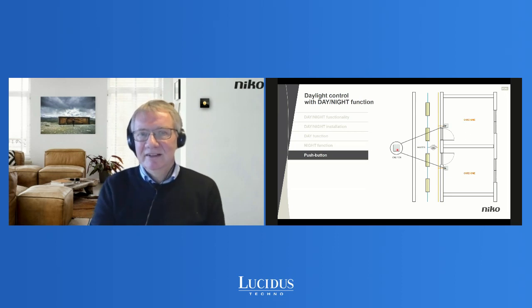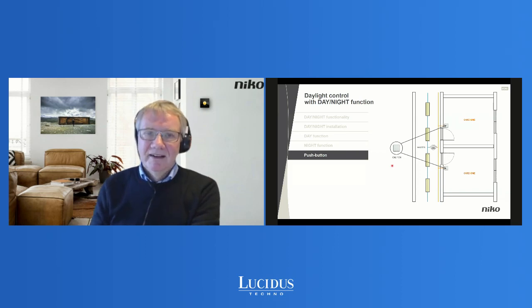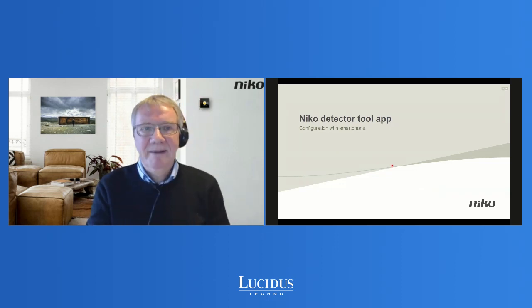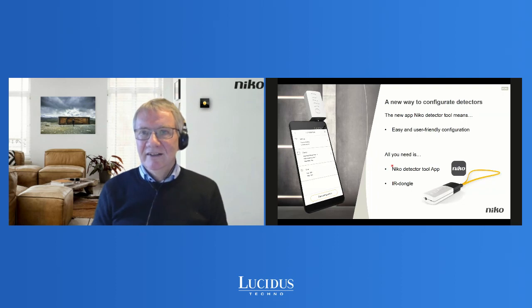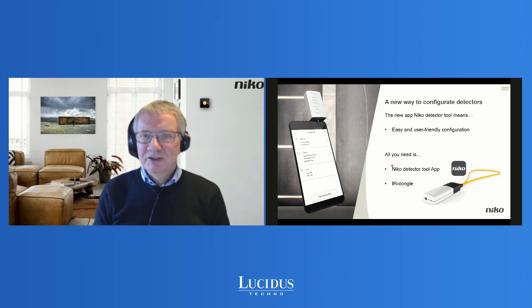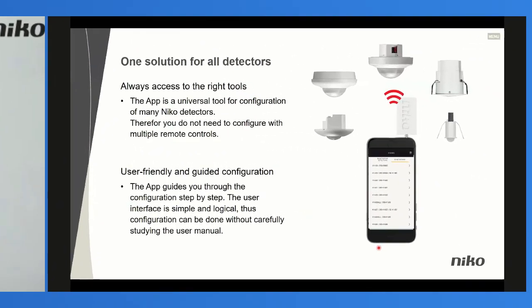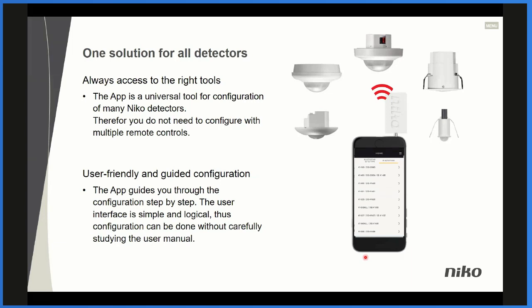The push button could be set so that it only has the possibility to turn on the light, not turn off the light, if that is necessary. In order to commission all of it, you use the Niko detector tool app, which can be used on any kind of smartphone. You use the app and the infrared dongle, and the dongle provides infrared communication to the detector. The app is not only for DALI detectors, it's a whole range of different detectors that can be commissioned by this app. It is user-friendly because you're guided through the app step by step, so you can do it in a structured way.